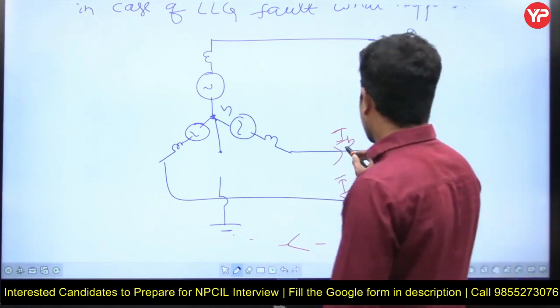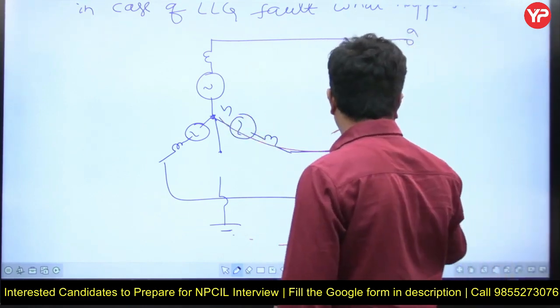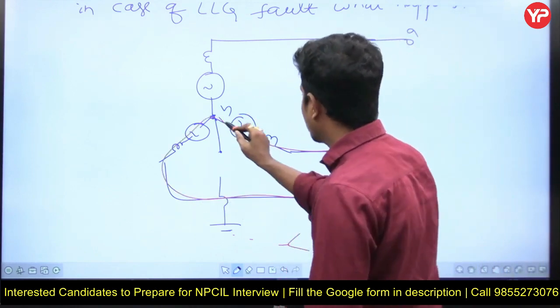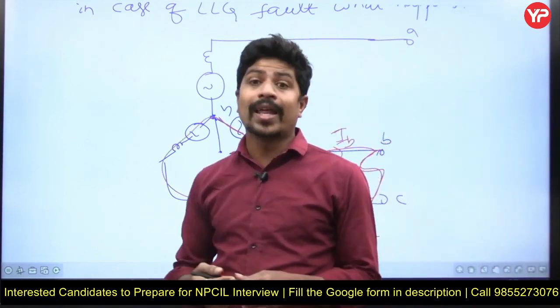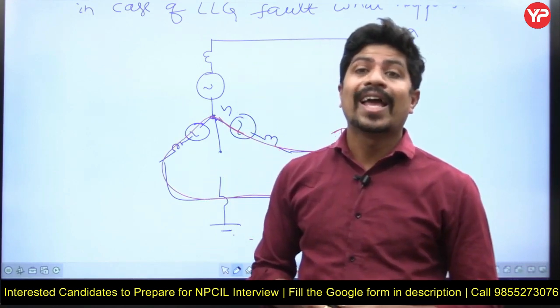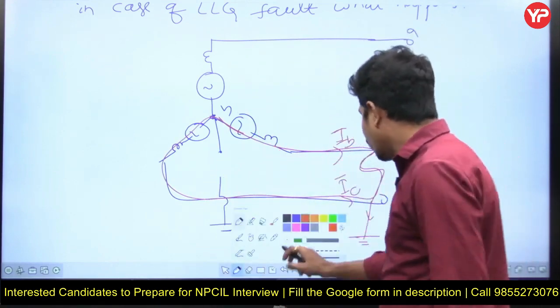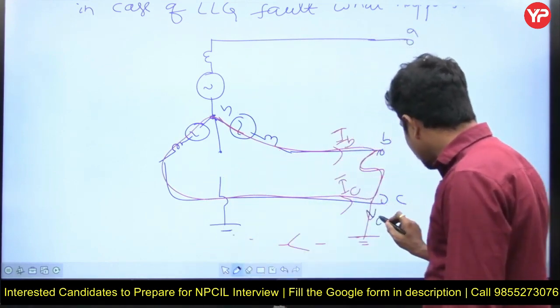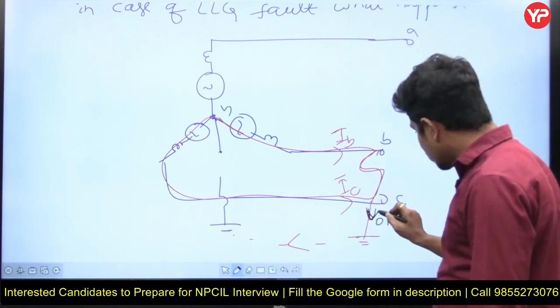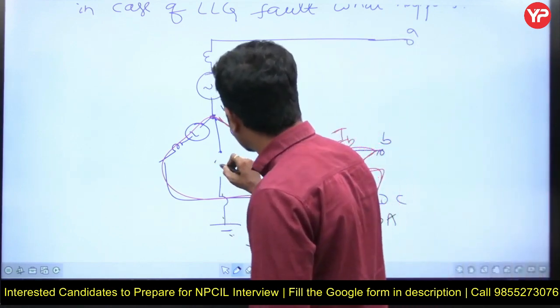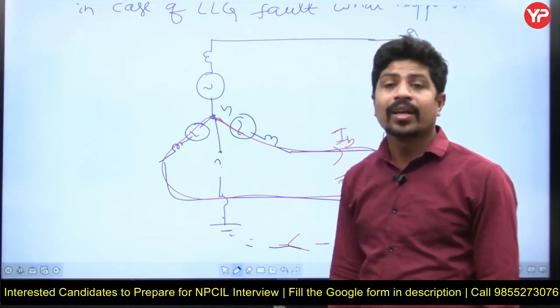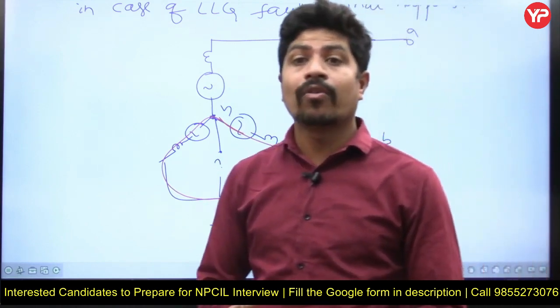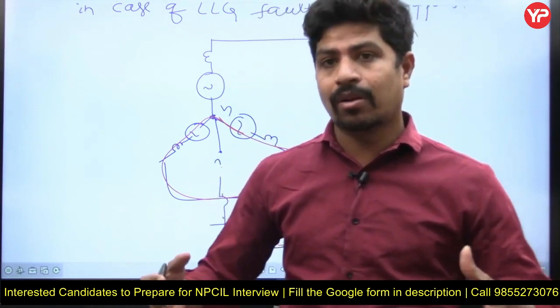What happens is the fault current will flow between B and C only. No more is it going to be an LLG fault. It behaves like an LL fault. Why? Because though physically it is connected, here the current is zero. Why? Because there is no closed path. Here an open circuit is there, right? So as there is no closed path, an LLG fault will behave as a simple LL fault, right?